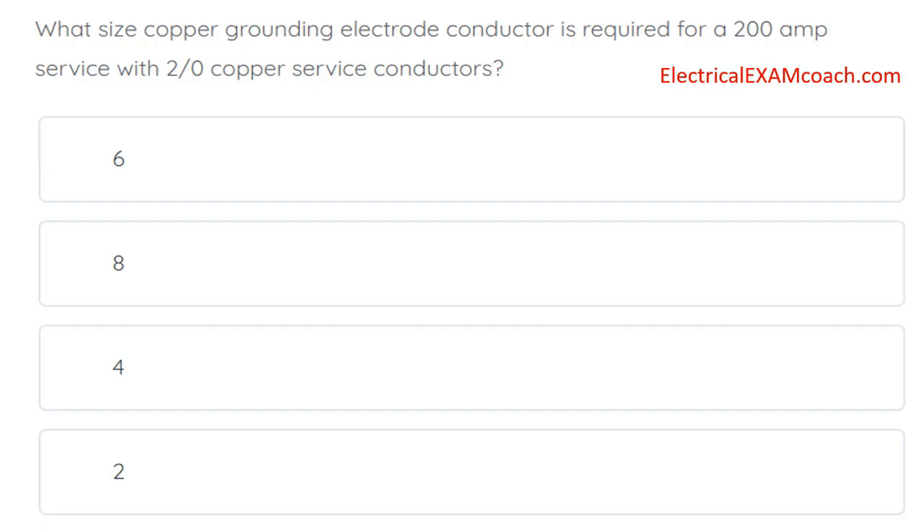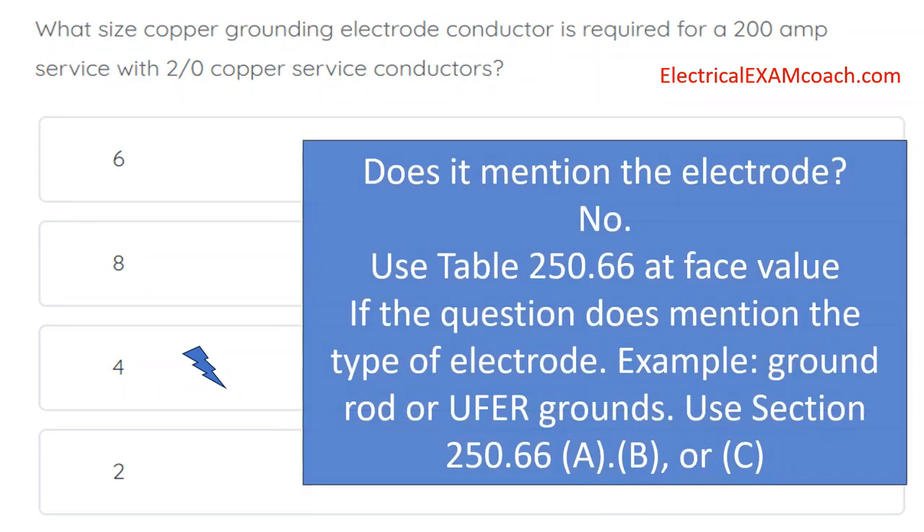What size copper grounding electrode conductor is required for a 200-amp service with 2/0 copper service conductors? The grounding electrode conductor is the wire that goes from the ground rod to the service enclosure. The correct answer is a number four. Anytime an exam question involves grounding electrode conductors, ask: does it mention the type of electrode? If not, default to table 250.66 and use it at face value. If it does mention a specific electrode type such as a ground rod or UFER ground, first check sections 250.66A, B, or C.